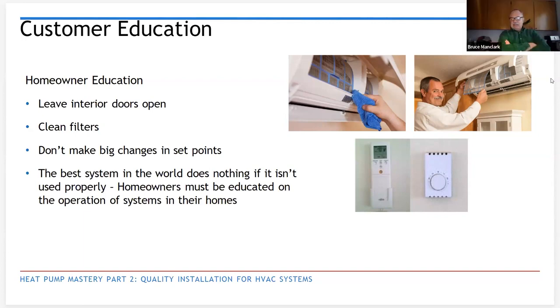You know, I know a lot of things I learned about heat pumps 40 years ago has changed, or they were just myths. But I think one of the best pieces of advice I got, and it still holds true today, is set it and forget it with the thermostat for heat pumps. Yep. Still works today. We have a variable speed system on our place, and I like it cooler at night. So we do drop maybe a degree or two in the bedrooms, but other than that, we're not touching that thermostat. Once it's set, just let it do its thing and make sure that filter gets changed.